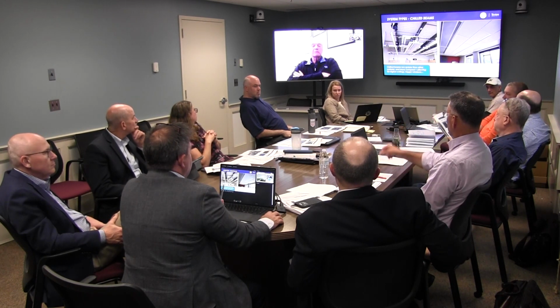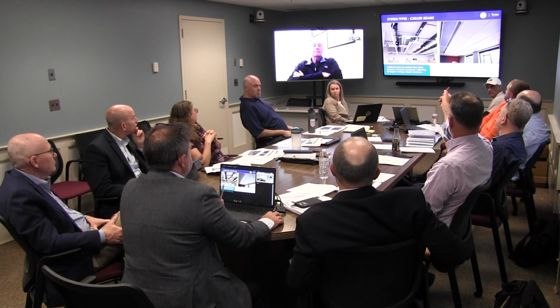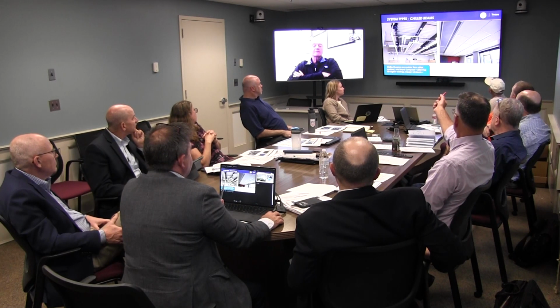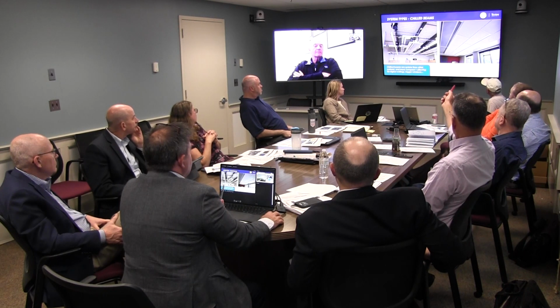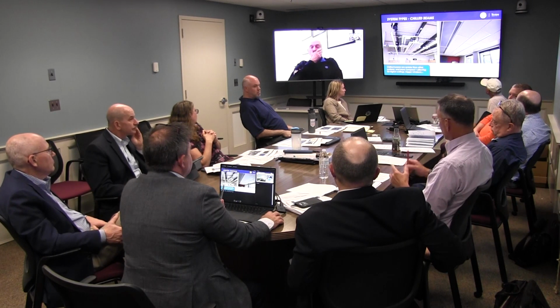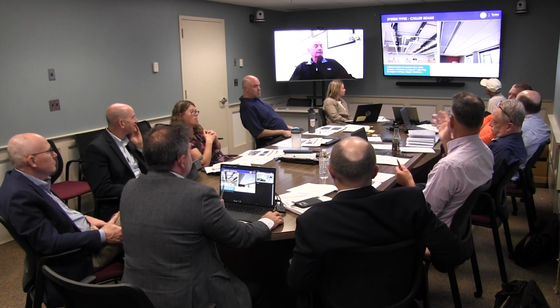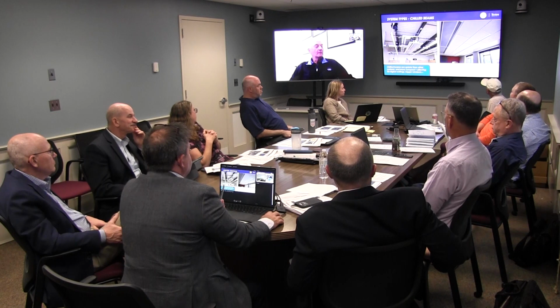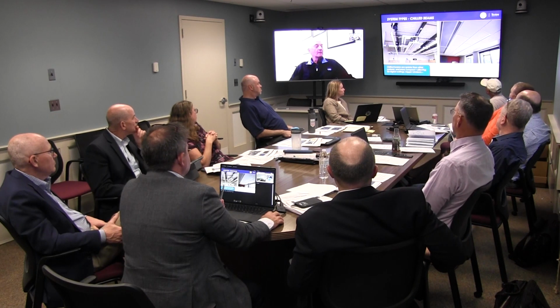Now, you remember on the walkthrough we did, I took a couple of pictures. This is an elementary school. So this is the chilled beam that they put in there, but that school did two things. They put radiant panels at the perimeter as well as chilled beams in there. So belt and suspenders, but some people like that because it gives you the option of doing it. But with real tight envelopes, you can get away without even using radiant panels. The nice thing about radiant panels is they don't take up floor space.